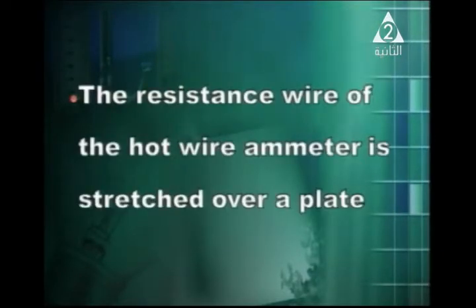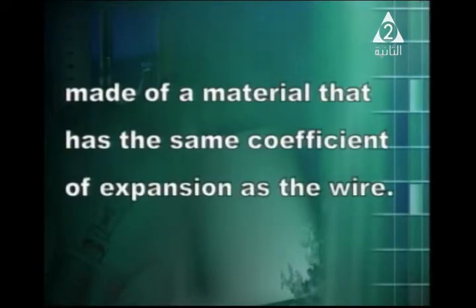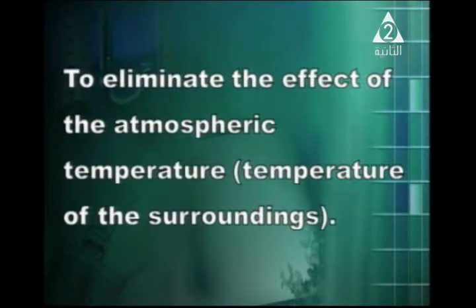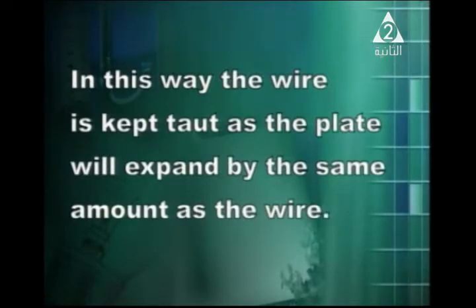Another reason: the resistance wire of the hot wire ammeter is stretched over a plate made of a material that has the same coefficient of expansion as the wire. This is to eliminate the effect of the atmospheric temperature of the surroundings. In this way, the wire is kept taut, as the plate will expand by the same amount as the wire.